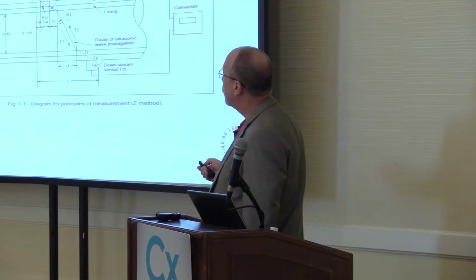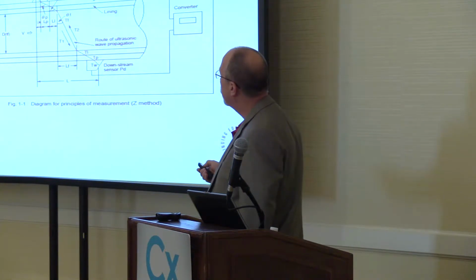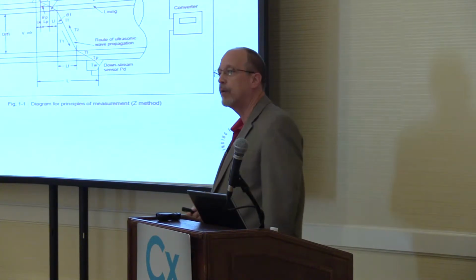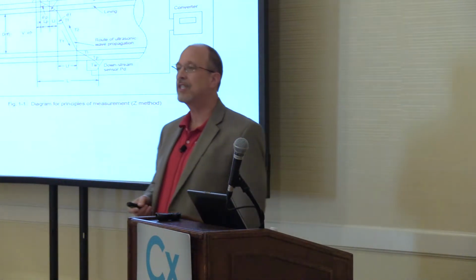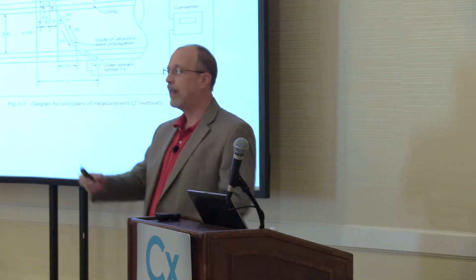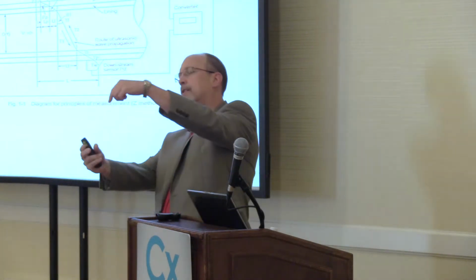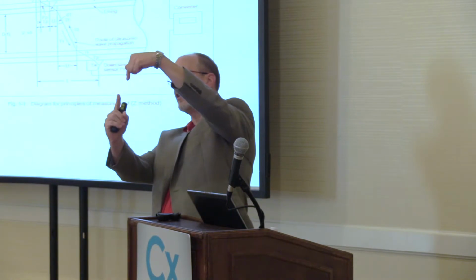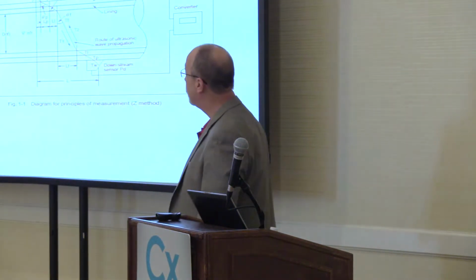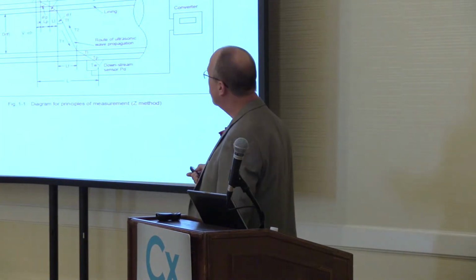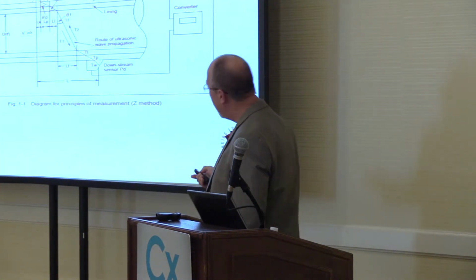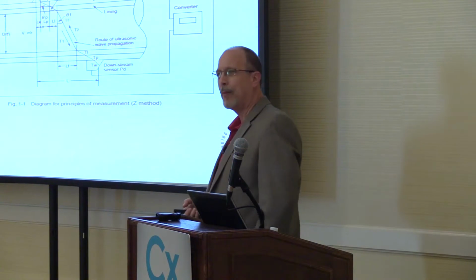So we send a signal through the pipe wall. In this case, this pipe has a liner. We need to know the sound speed of this carbon steel pipe. Come through the pipe wall, and when it hits the processed liquid, something occurs. It's called Snell's law. You ever take a glass of water, put a straw in it, look at it sideways, and the straw is kind of cockeyed, cut off? That's Snell's law. It refracts. So old Snell is factored into this equation. You need to know the sound speed of the liquid and the whole thing back up. That's a lot of math.